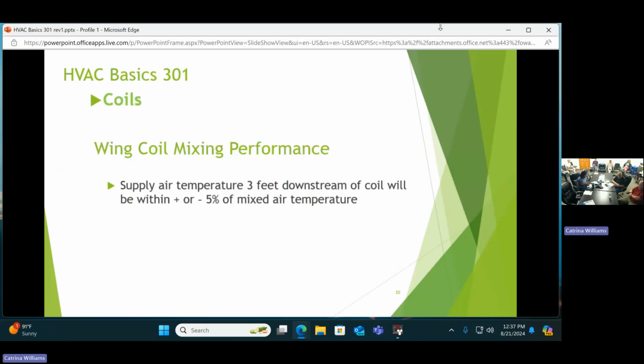Here's the good news about it. That's what Doug was pointing out, that the supply air temperature 3 feet downstream of the coil will be within plus or minus 5% of the mixed air temperature. Very little variation on those two temperatures, just 3 feet down from the coil. The airflows do mix that well, just with the damping range. But if you put the anti-stratification baffles on there, it's even a little bit less than that.